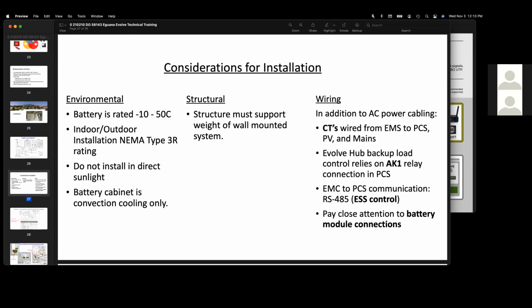Jel, I hope I'm pronouncing your name right, asks: is it possible to parallel two systems with two PV inverters, two hubs, two Evolves, and two backup electrical panels to supply 10 kW of backup loads? 10 kW total, yes. If you have two backup electrical panels, you would have 5 kW in each, and it would provide that total of 10 kW. If that's your constraint, then yes, absolutely. You can put two systems in parallel onto one service panel. You'll just have to look at the bus rating of that main service panel in order to put two 40 amp interconnection breakers on there.